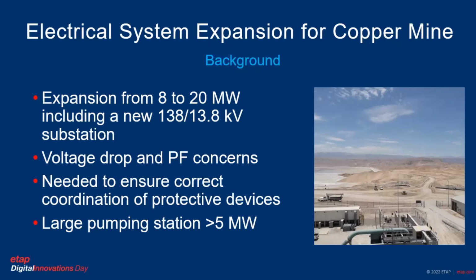In the present situation, they observed excessive voltage drop during normal operation, which was really worse when some of the large motors were connected to the electrical system. The voltage drop was excessive. So, for example, in the pumping stations, we have motors at 4160 volts and 1,250 horsepower.